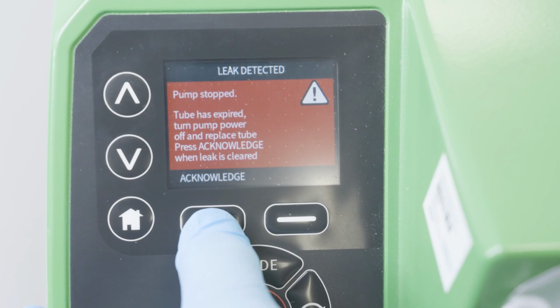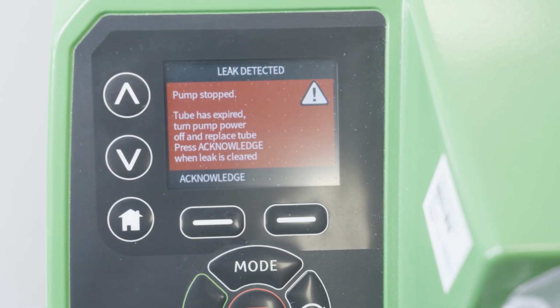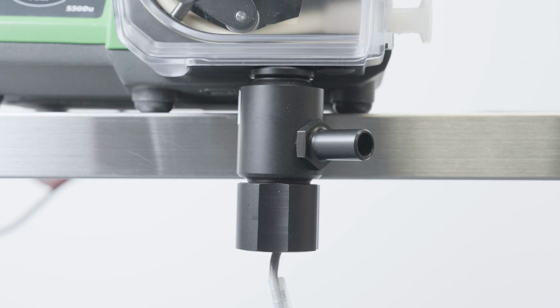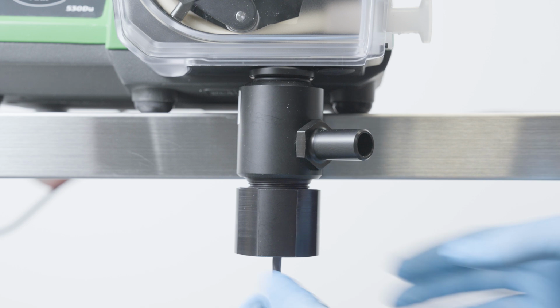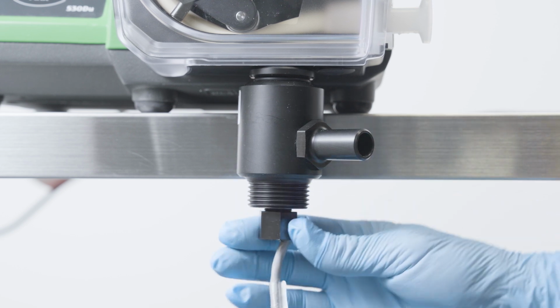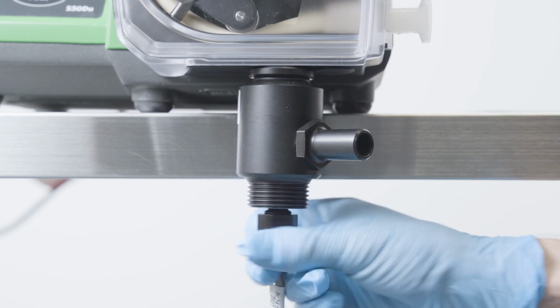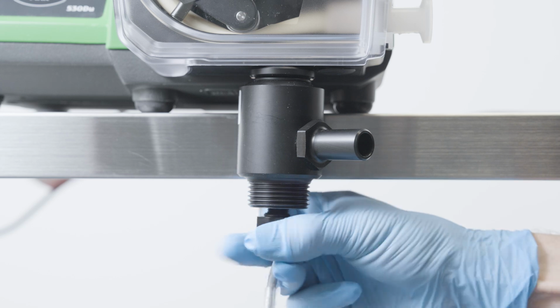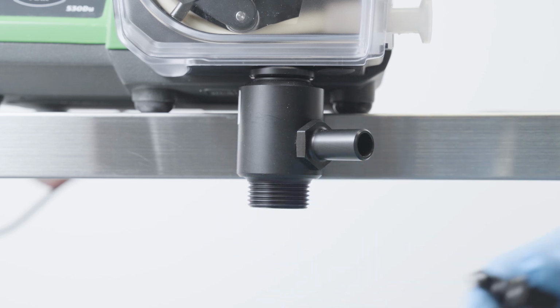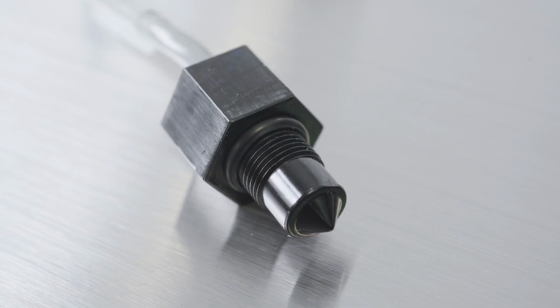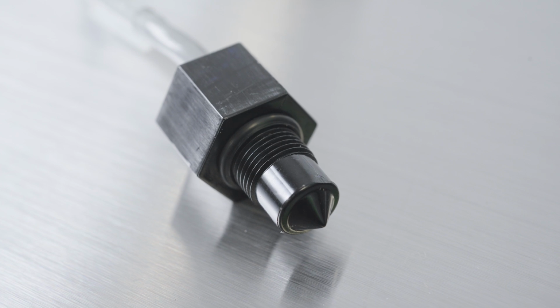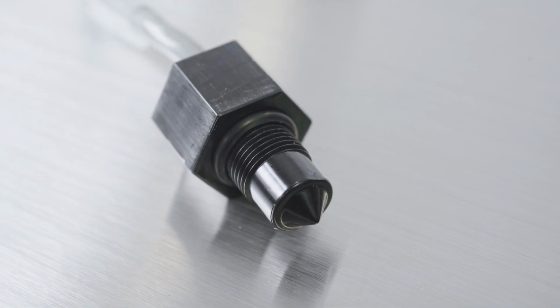If the leak detect persists, you may need to wipe down or flush out your leak detector. There are two types of leak detector associated with a 520 pump head: an optical leak detector and a float leak detector. Both leak detectors unscrew from their position at the underside of the pump head. With an optical type leak detector, follow your cleaning protocol to remove any fluid, ensuring the lens is clean, dry and free of any debris or chemical attack.